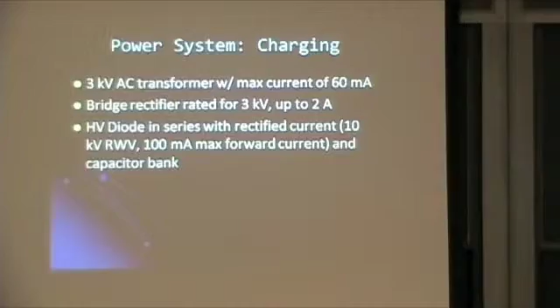So the charging system consists of a 3 kilovolt AC transformer. Its max current output is 60 milliamps, and we have a bridge rectifier to keep positive bias because these capacitors can't be reverse charged. The bridge rectifier is more than capable of handling this because it's rated over 2 amps.